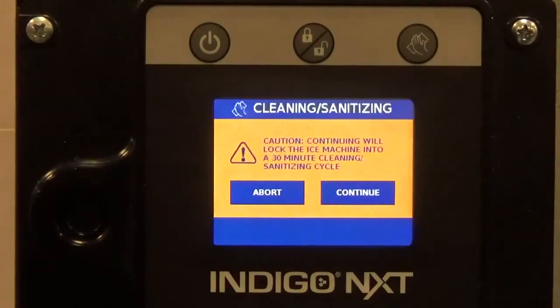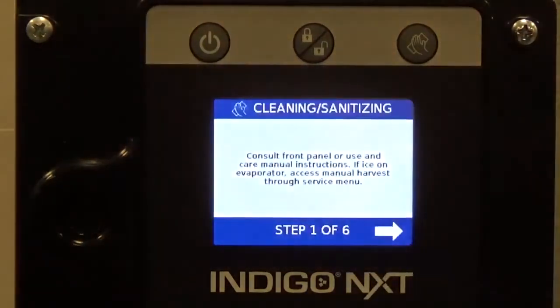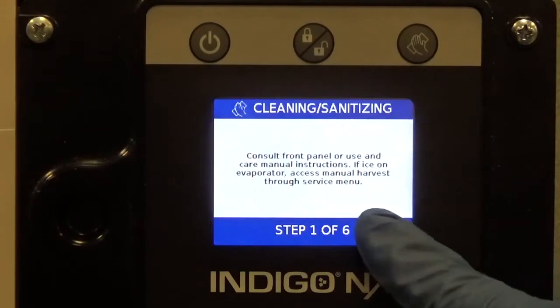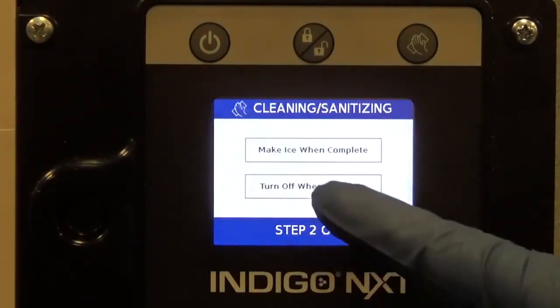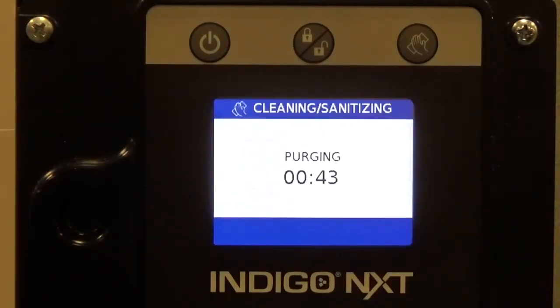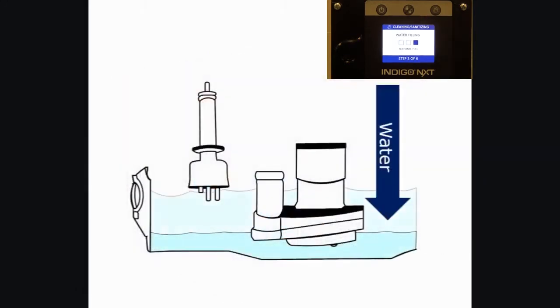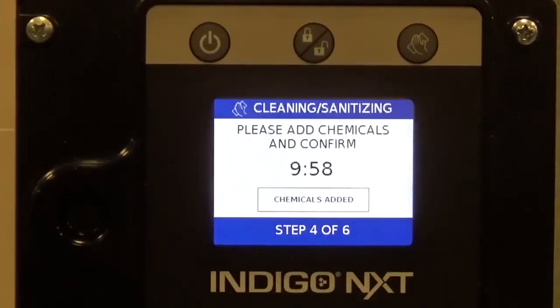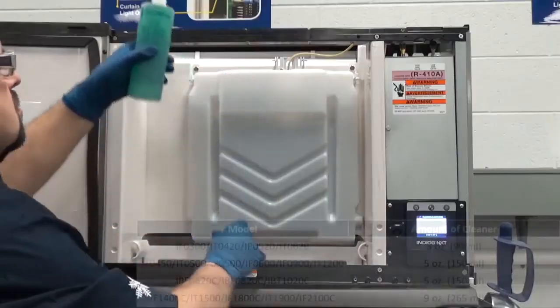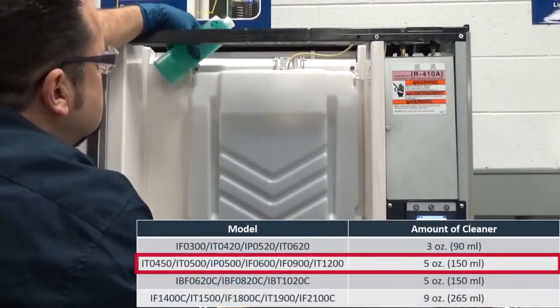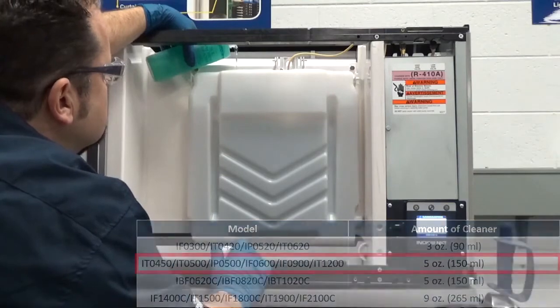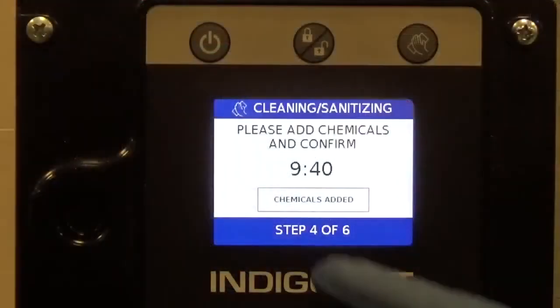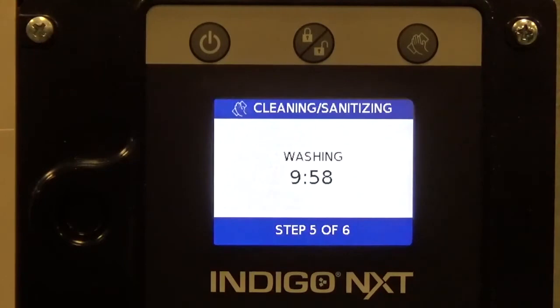Step 3. Press the clean button and follow the prompts. Select continue and then press the right arrow. Select turn off when complete. Water will flow through the water dump valve and down the drain. Wait approximately 1 minute until the water trough refills and the display indicates add chemical. Add the proper amount of ice machine cleaner to the water trough by pouring between the water curtain and evaporator, then confirm that the chemical was added.